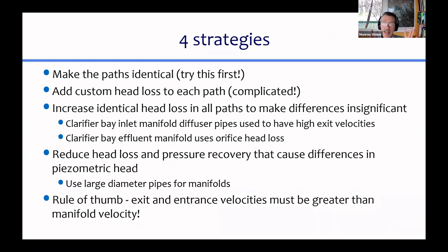So if you have a way that you can make all the paths identical, that's an interesting option, because that completely solves this problem. If the paths are identical, you have no problem. You could add custom head loss to each path. That's complicated. You could increase the identical head loss in all paths to make the differences insignificant.